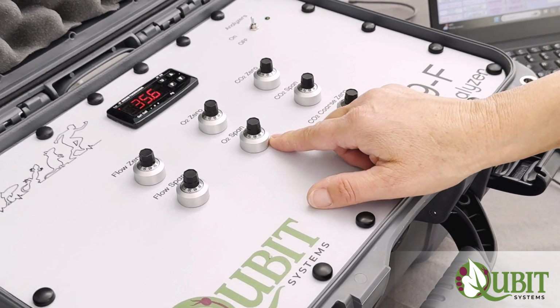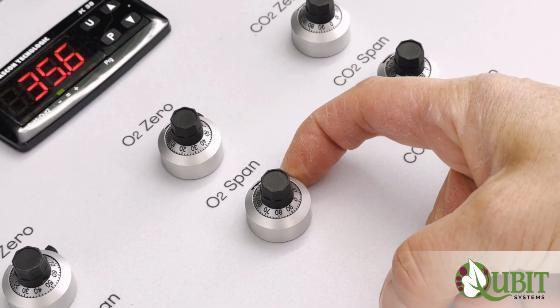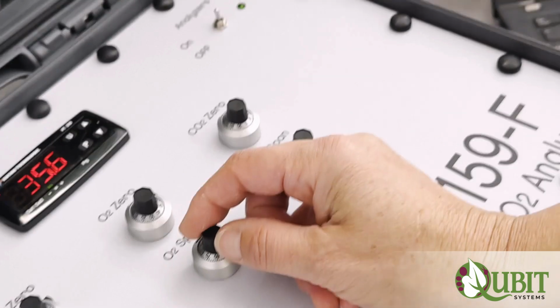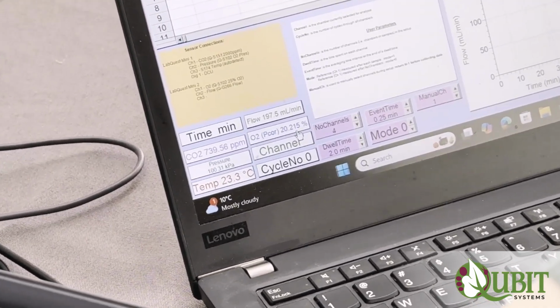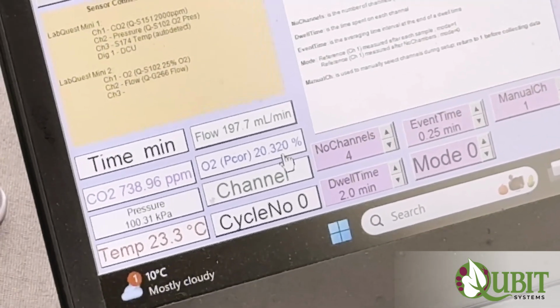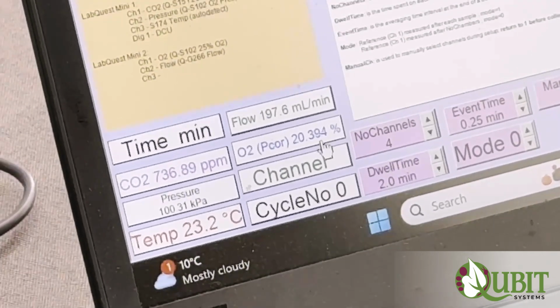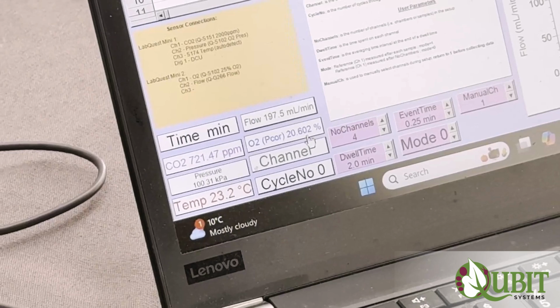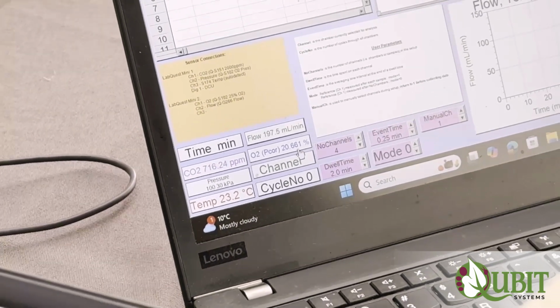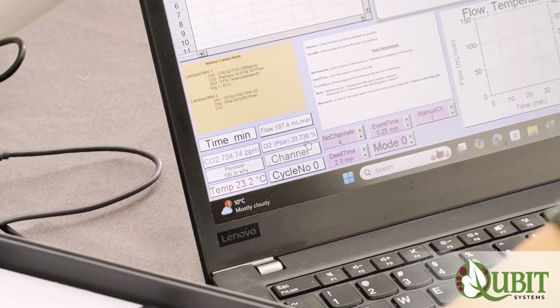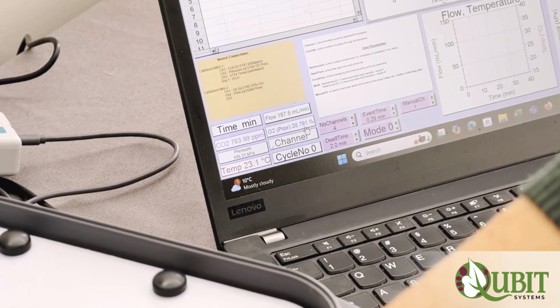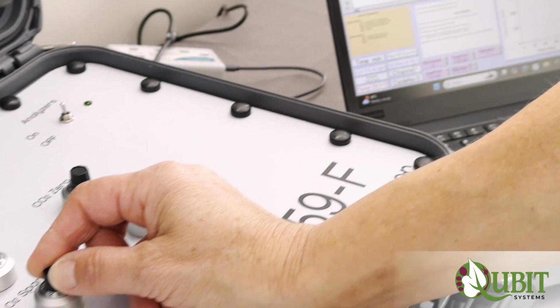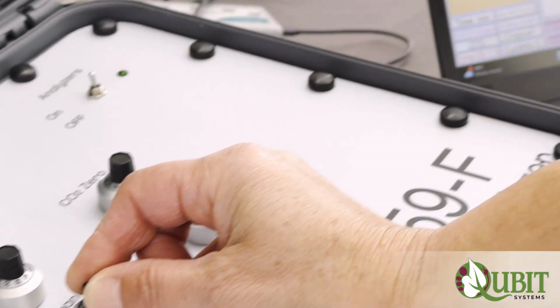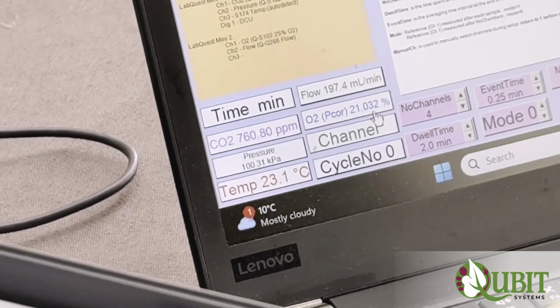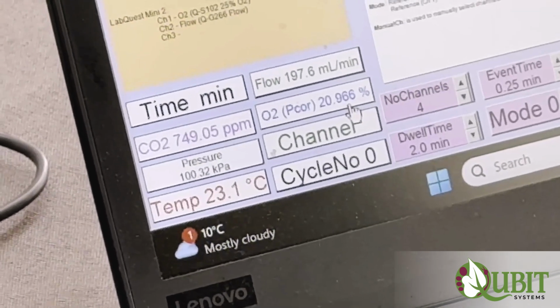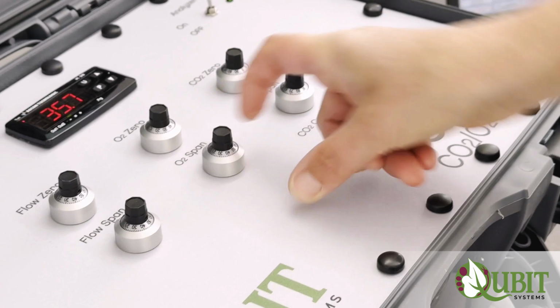So to adjust the oxygen reading here and to adjust our oxygen span, we go to our O2 span. We release the tab again by pushing it up. And this time we need to increase the reading to 20.95. So we're turning it clockwise, 20.3. And you do this slowly so you don't overshoot, otherwise you have to come back down again. About 20.95 is what we're aiming for, because that's the level of oxygen in dry outside air. So one only needs to have really one gas tank to calibrate both CO2 and O2 sensors. Here we go, 20.96, I've just gone over. So I'm going back down again, 20.95. So lock the tab back in once the O2 span has been set.